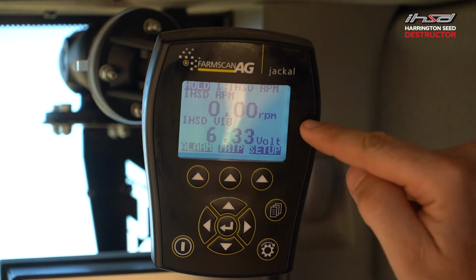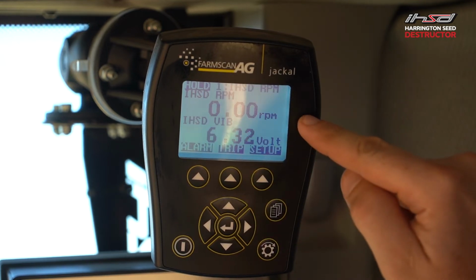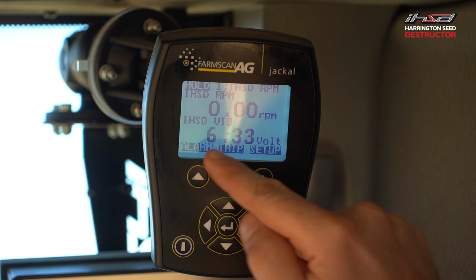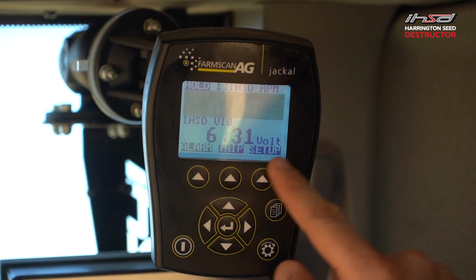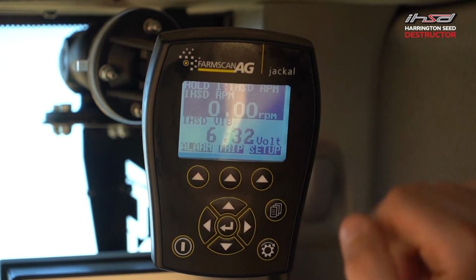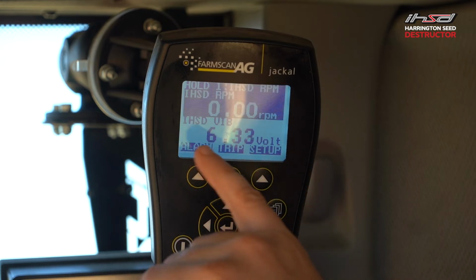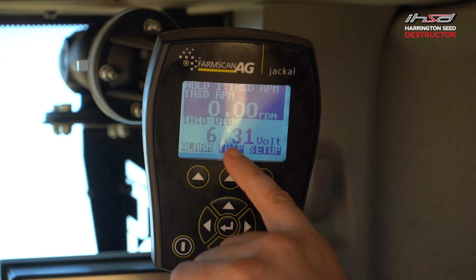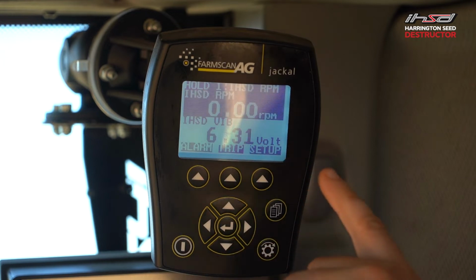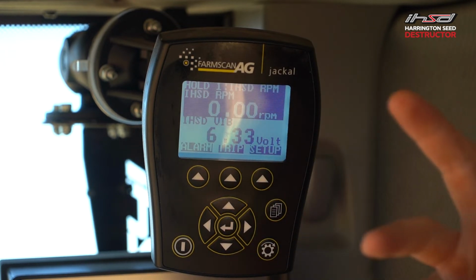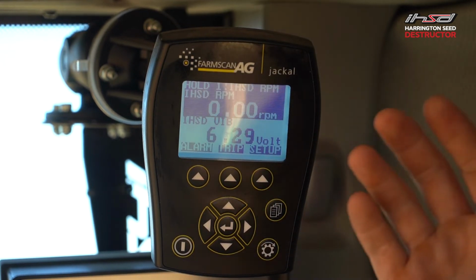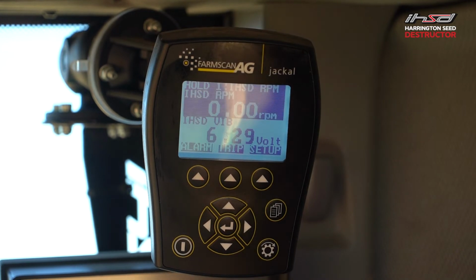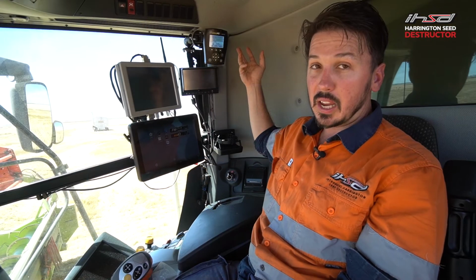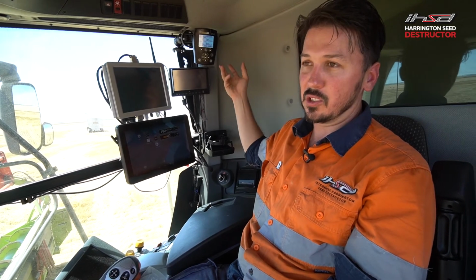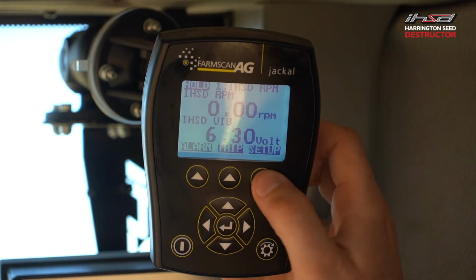At the top, we have the RPM, which is fairly self-explanatory, and we have the iHSD vibration. This is where we have the largest amount of issues, is the misunderstanding of this. The readout we have for the vibration is just a number that doesn't really represent anything. It just needs to show above 1 volt or below 1 volt. Once it gets to below 1 volt, then that means the alarm should come on and you have a vibration issue. Moving on to the setup.